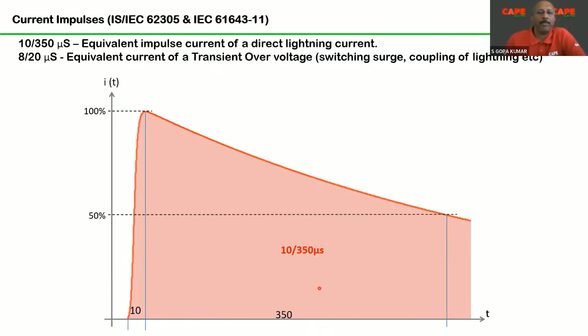by 350 microseconds. It means in 10 microseconds, the current, probably 100 kiloampere, goes from 0 to peak, and it comes to half value in 350 microseconds. So basically 10 by 350 is an equivalent current wave shape of a lightning strike. Don't think that lightning will always be 10 by 350. It is not like that. This 10 by 350 is an equivalent representation of the energy content of a lightning in the form of an impulse current.